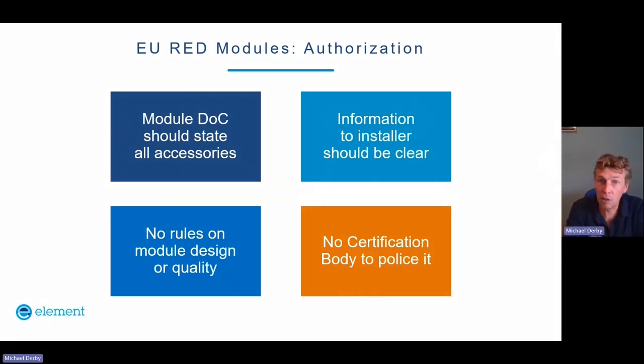Even if you go to a notified body, they're just performing a technical assessment to Article 3.1, 3.2 and 3.3. Obviously the notified body will read things like the label and the user manual, and they'll work with you, but they'll only prevent the certificate if there's a risk of non-compliance to Article 3.